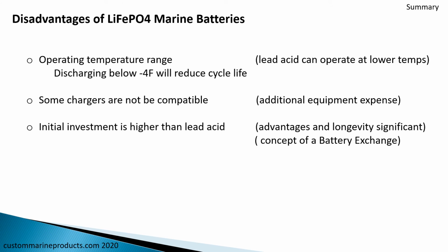There are a few disadvantages of these batteries, and one is the operating temperature that we've talked about. You really don't want to discharge them below -4 degrees Fahrenheit. Some chargers may not be compatible with these, especially your older analog-based chargers. I wouldn't use them with lithium iron phosphate. Our initial investment is higher than lead acid, but the advantages and the longevity often offset this.